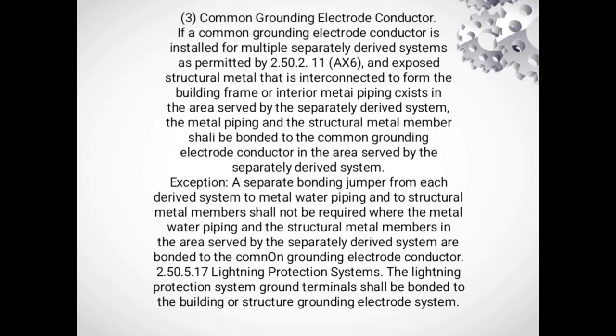2.50.5.17 Lightning Protection System. The lightning protection system ground terminal shall be bonded to the building or structure grounding electrode system. Section 2.50.5.15 addresses the use of a common grounding electrode conductor. Section 2.50.5.17 addresses the lightning protection system. Bonding to a common grounding electrode conductor is essential for minimizing ground loops. The lightning protection system ground terminal must also be bonded to the building grounding system.